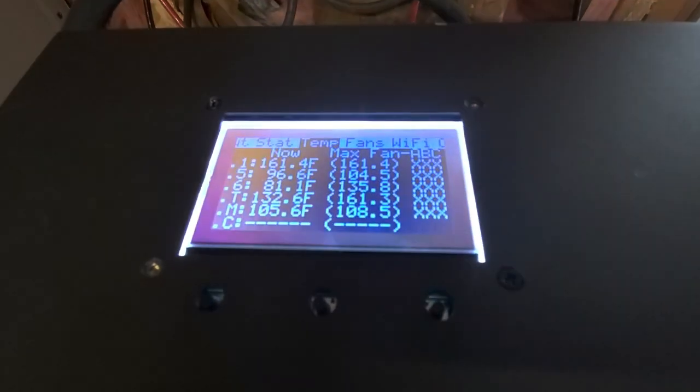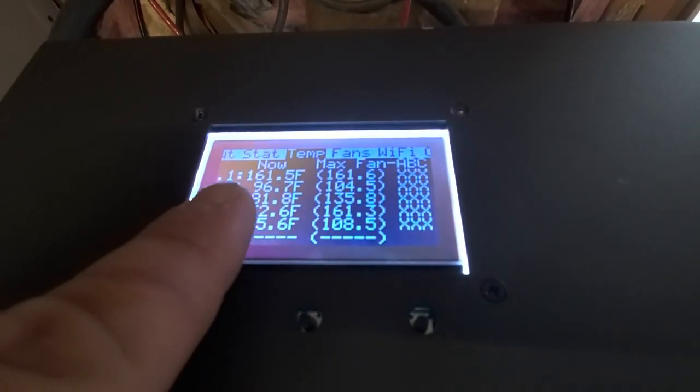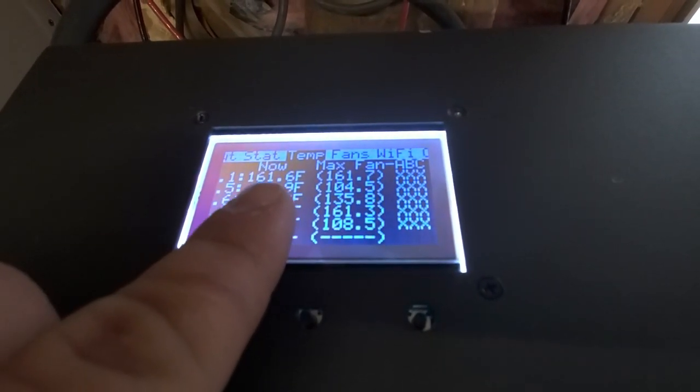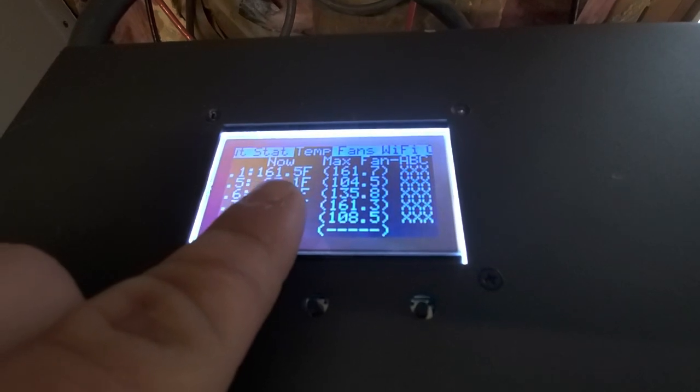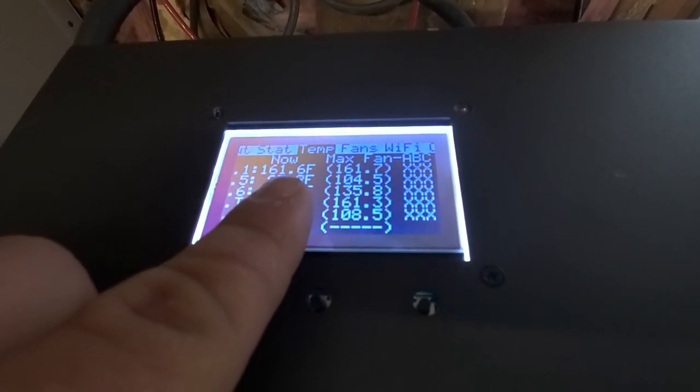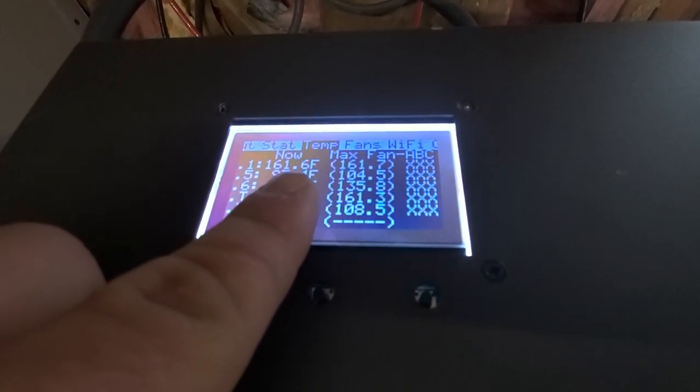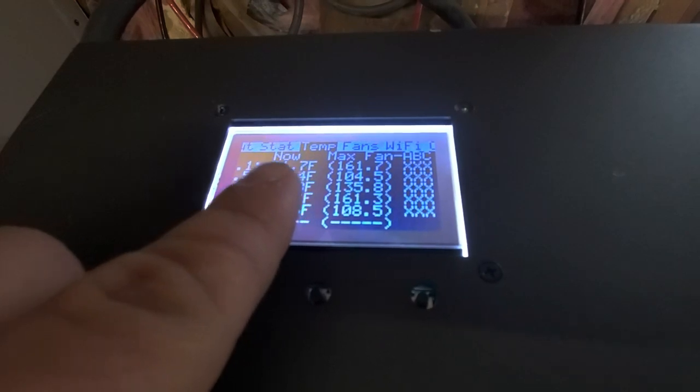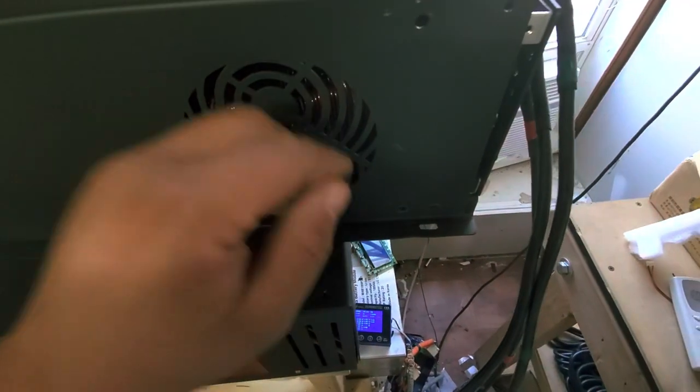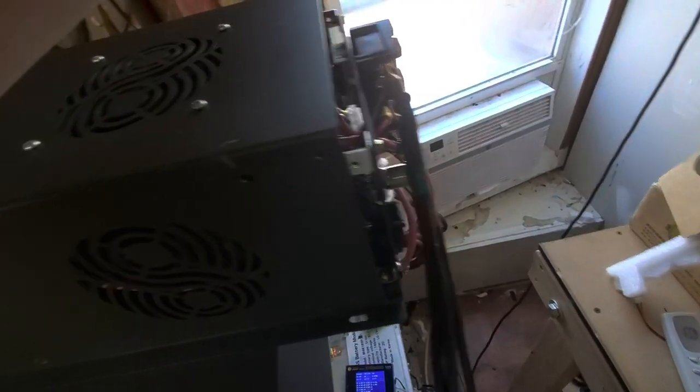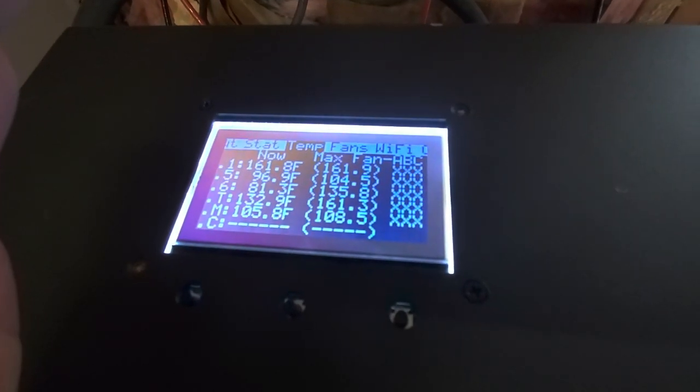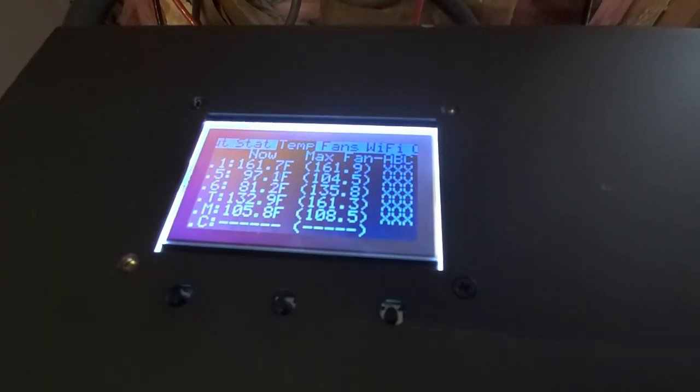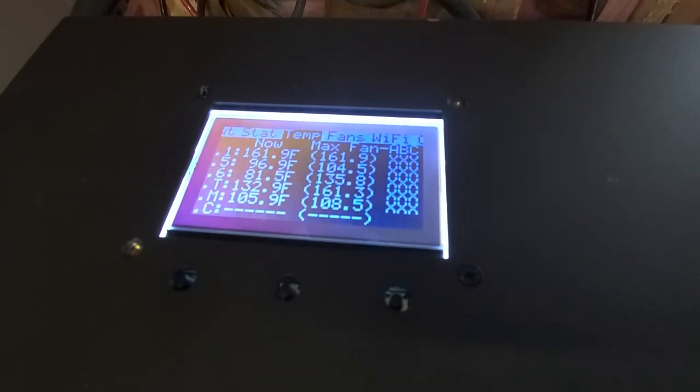Right now I'm watching the temperature of the transformer, which is climbing. If this continues up to 165, it's going to shut down. Fans are maxed out right now. I have it set to 165 for safety, but I am going to push it up to 170 and see what happens.